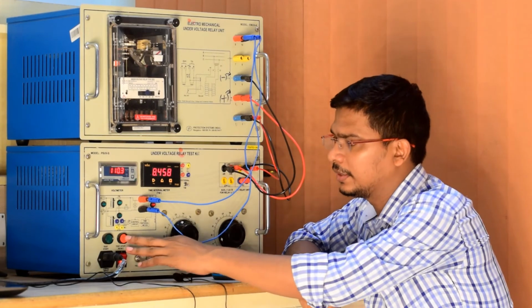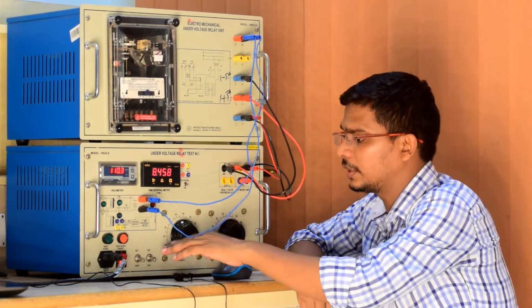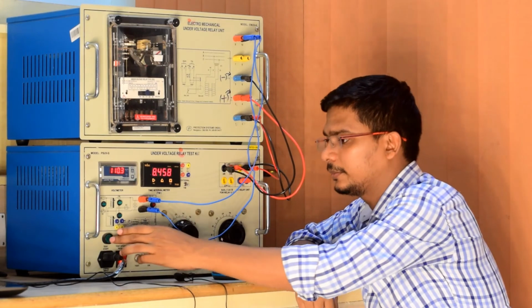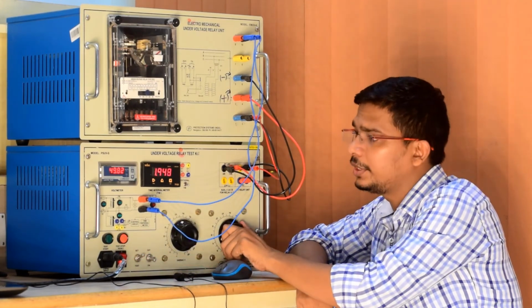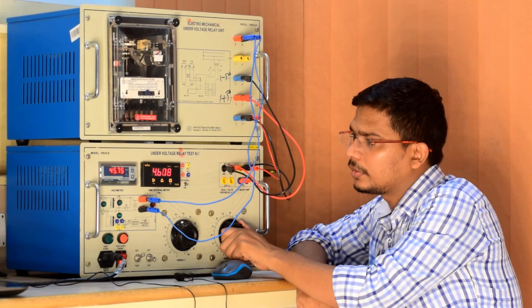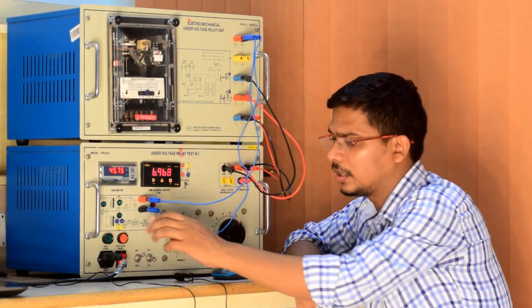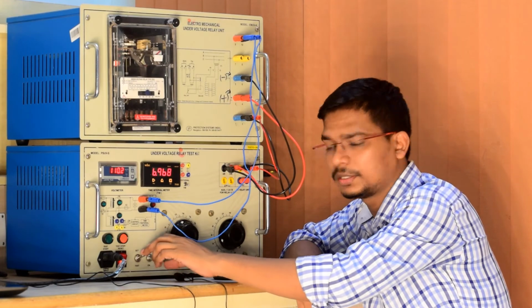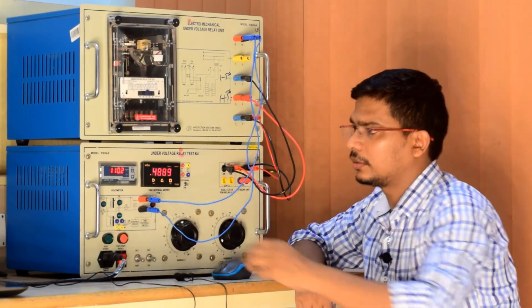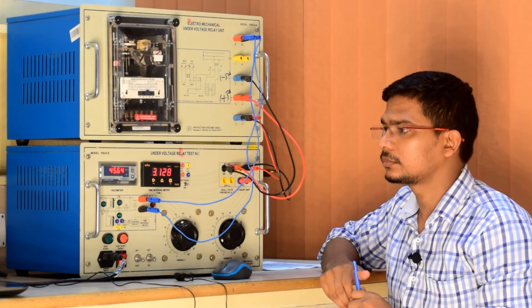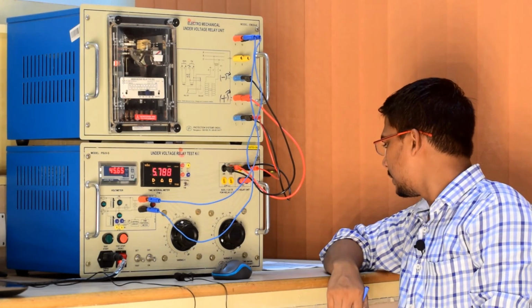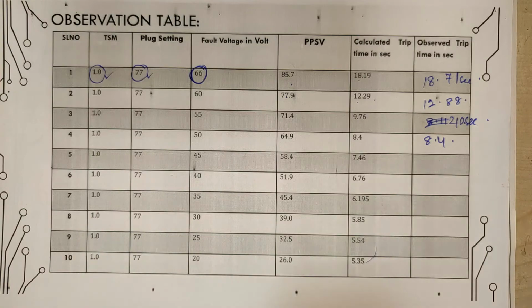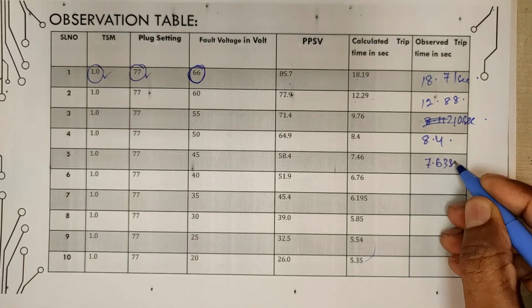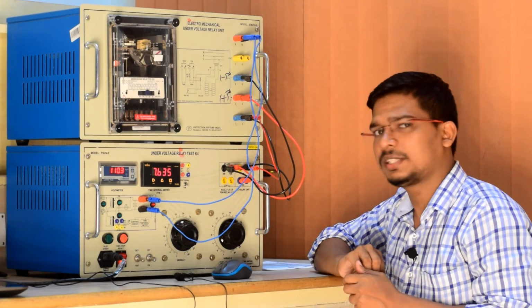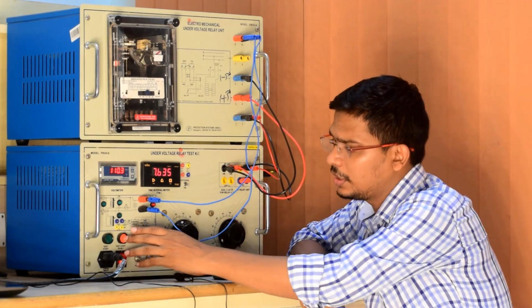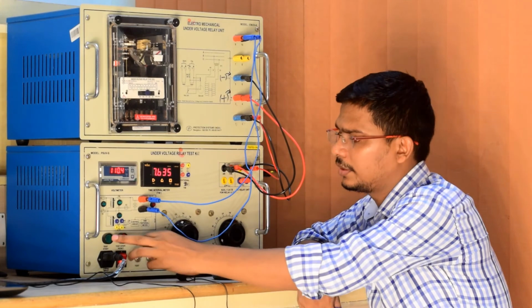We can directly rectify it. Next, turn off for the 45 volt, set, turn on, and 45 volt. So this is 45 volt. Turn off, this should be in test mode, then turn on. Our expectation time is 7.46 seconds, and we got 7.63 seconds. So exactly what we are expecting is coming. Next observation: turn off, set this one.